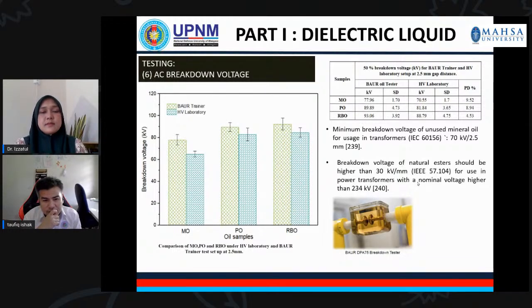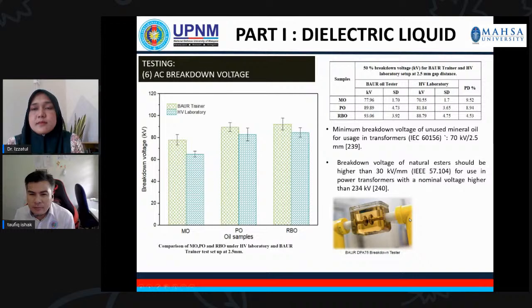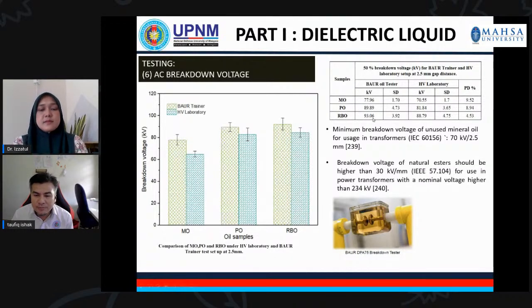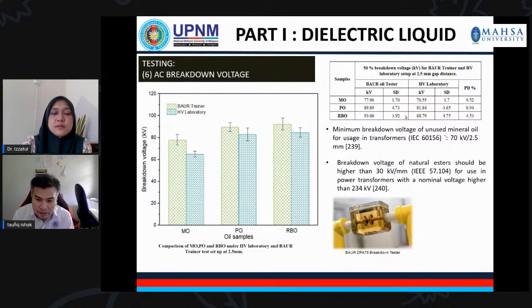And from this study, what we can see on the table is that the mineral oil, by using the BAUR tester, is higher than the high voltage lab, due to a few reasons. One of the reasons is that when you are using the bulk tester, normally they have a stirrer at the bottom of the test cell, and for high voltage, normally we don't use the stirrer. So that's the reason. When you use the stirrer, the black carbon, or the carbonized oil after the breakdown, will disperse in the area of the electrode, as compared to the high voltage lab.